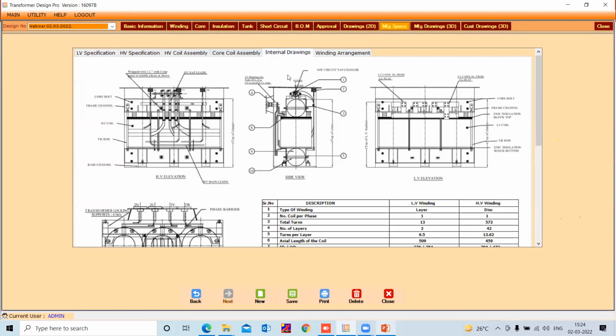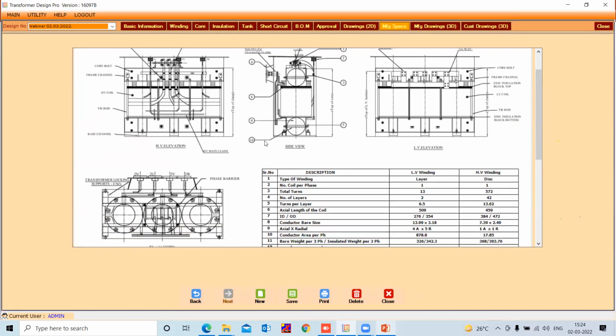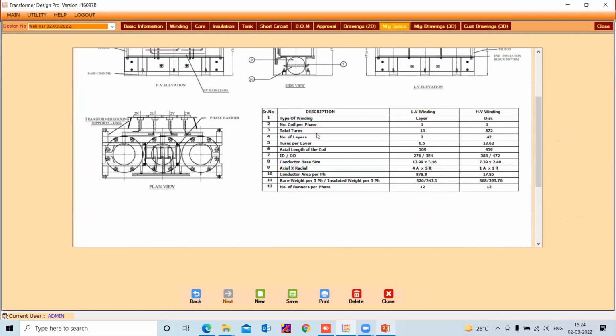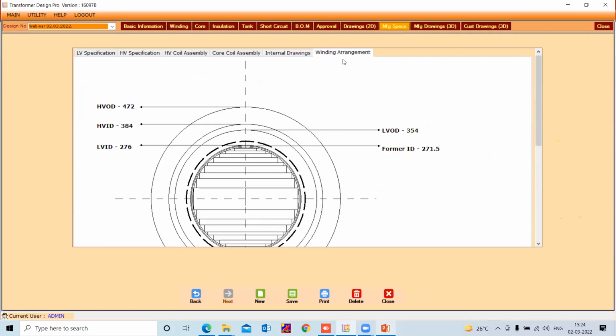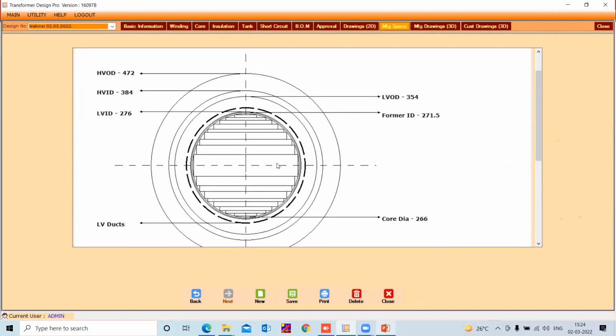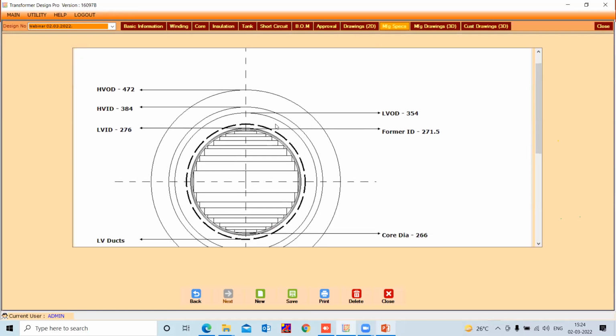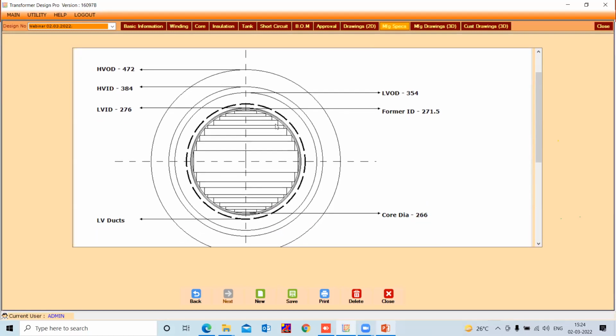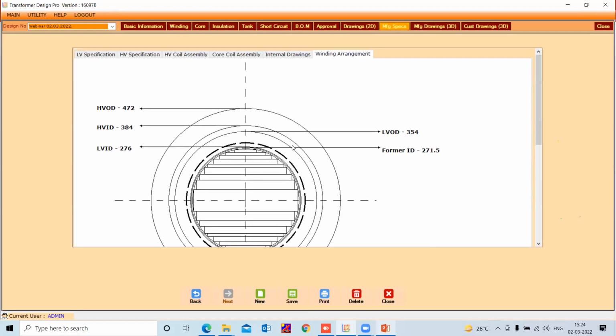Next is the internal diagram. Here you will get the HV and LV elevation, side view and top view, and the LV and HV winding detail. Now next is the winding arrangement. This is also generated based on the stack calculation, how many steps and what blade width we have selected. Based on that, this diagram will generate. And what kind of core construction you have selected on the basic information page, like wound core, circle, or elliptical core, based on that, this diagram will change automatically.